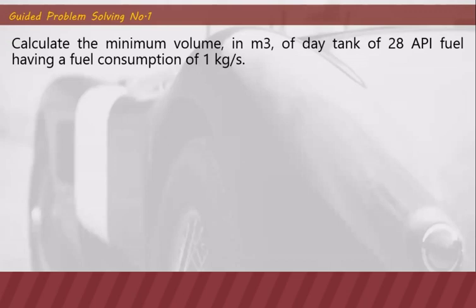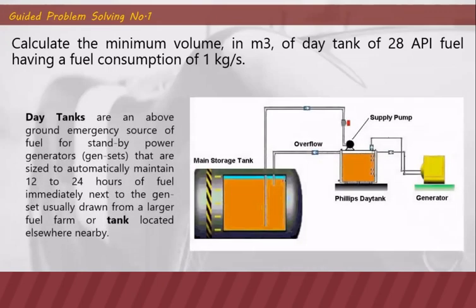Guided problem solving number one: calculate the minimum volume in cubic meters of a day tank of 28-degree API fuel having a fuel consumption of one kilogram per second. A day tank is an above-ground emergency source of fuel for standby power generators, sized to automatically maintain 12 to 24 hours of fuel immediately next to the genset, usually drawn from a larger fuel farm or tank located elsewhere nearby.